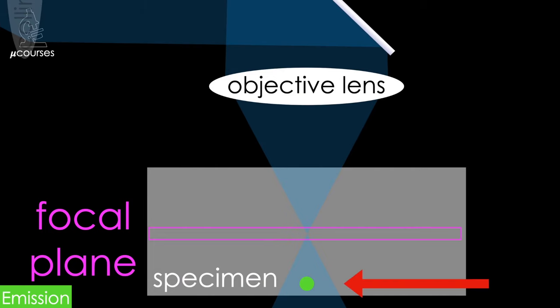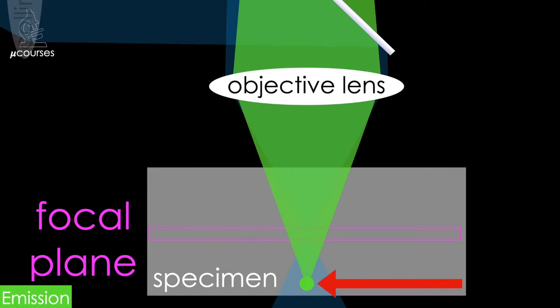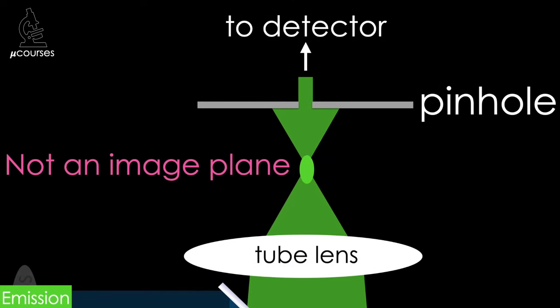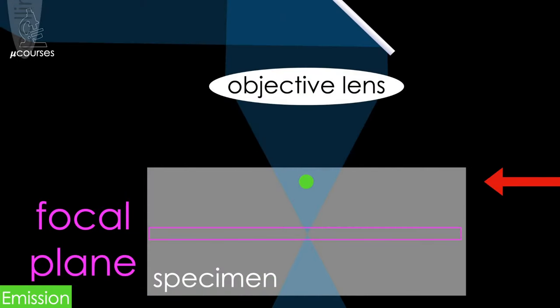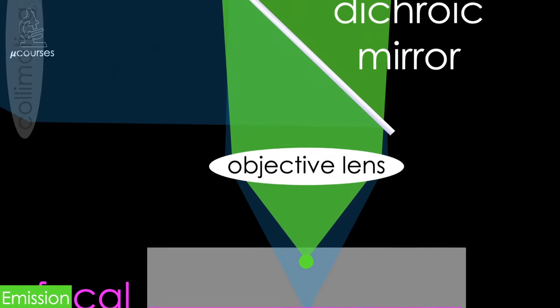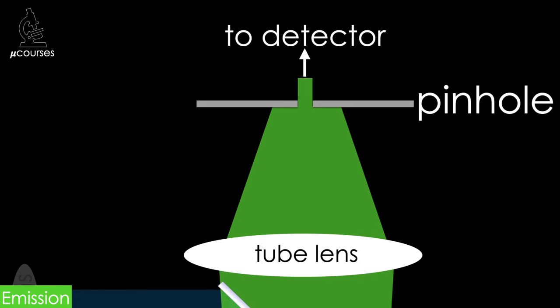Any objects outside the focal plane that are excited by the laser also emit photons collected by the objective lens. However, images of these objects focus outside of the image plane such that the image is out of focus when it reaches the pinhole. The pinhole therefore blocks the majority of light emitted from out-of-focus objects, preventing this light from reaching the detector. Whether objects reside above or below the focal plane, the pinhole blocks the majority of the out-of-focus fluorescence. Note that the pinhole cannot block all of it — so it's incorrect to say that confocal microscopes eliminate out-of-focus fluorescence, but they can greatly reduce it.